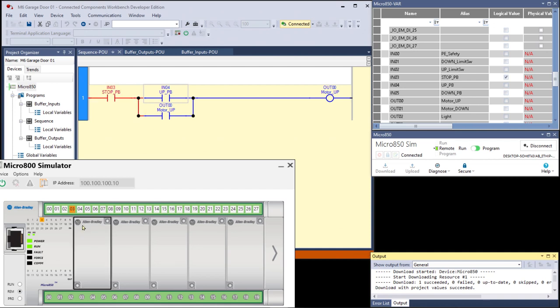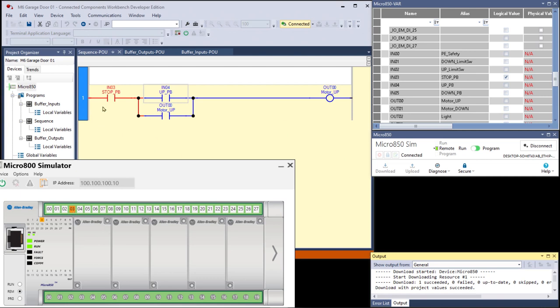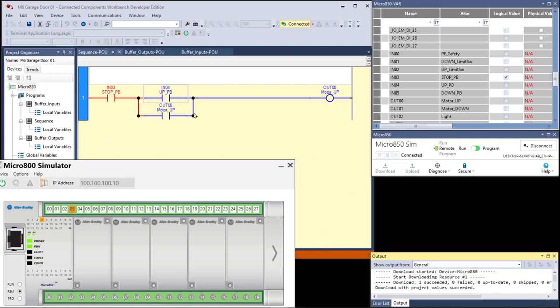Notice how our buffering has worked. This is not IN03. It's underscore IO underscore EM for embedded and underscore DI for digital input underscore 03. That's what I turned on, but because we're buffering our inputs, this turns on to fully represent the state of that screw terminal as far as high or low. Now in order to get the motor on, one of these is going to have to be true. Now since these both use the same address, when you see stuff like this, this is called seal in logic. You are sealing in the state of this rung with this contact from the load.